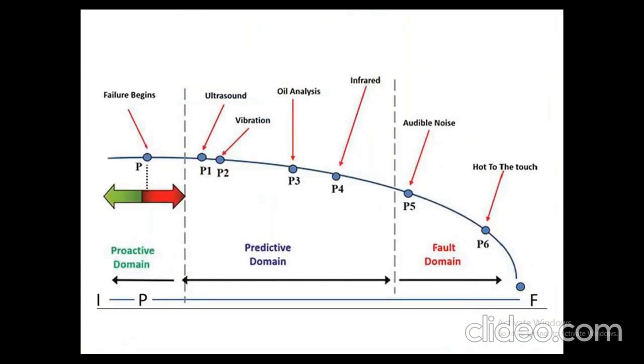This is the explanation of what we say. The failure begins and can be monitored by ultrasound, then comes vibration analysis, then oil analysis, then infrared, then audible noise. Why do we say some of the motors are really noisy? We are already at the tail end, at the breakdown that is going to happen. At point P5, it is at the point of breakdown. We are seeing the motors at the point of breakdown.